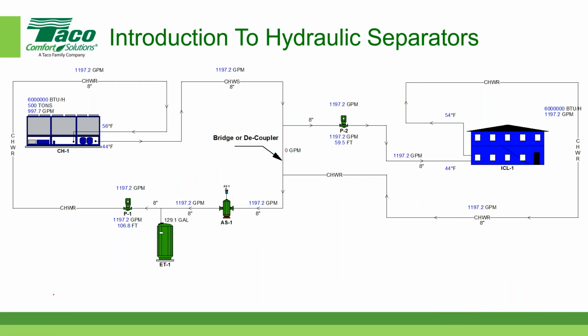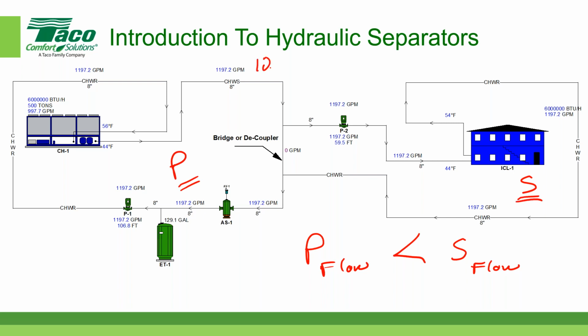All right, and the third case is when the primary flow is less than the secondary flow. Well, let's try that one out for size. Let's assume for a moment that the primary side over here was 1,200 gallons per minute, 1,200, and then something changed on the secondary side. Let's say somebody added on to our building at some point, and the secondary flow, and I'm just making up these numbers so you can get an idea of what's going on here, let's assume the secondary flow was 1,800 gallons per minute.